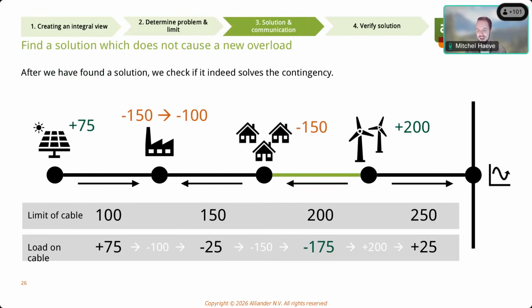Yeah, thank you. And indeed, that would look a bit like this. So let's say I used one of these products, for example redispatch, for example capacity limiting contracts, and I would ask this factory to go down by 50 units, 50 amps, for example, then I would have solved my problem. In our system, we always check if we actually solve our problem. So we find a solution and then actually check if that solution is also going to work. And over here you can see the load on the cable stays below the limit, which is perfect, meaning we actually solved the problem.